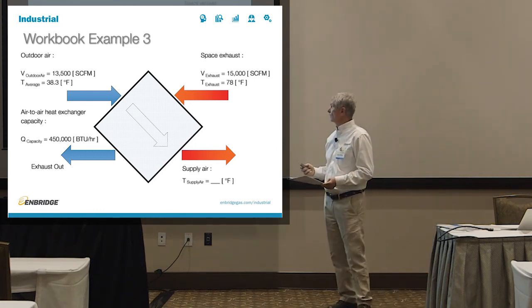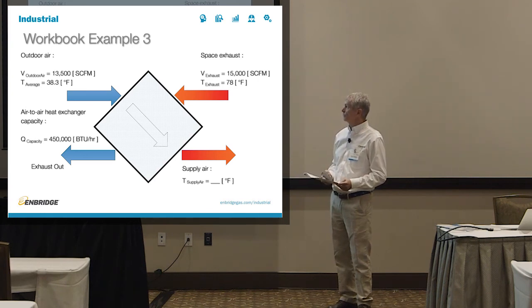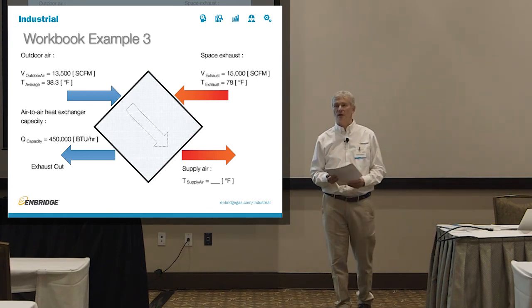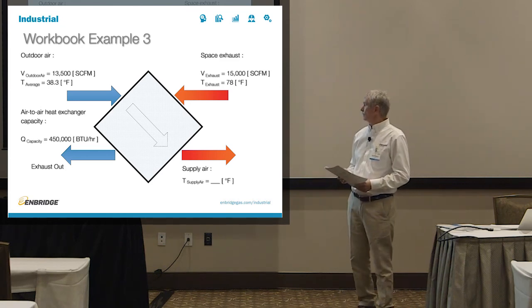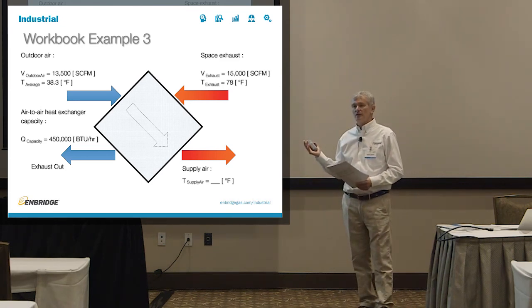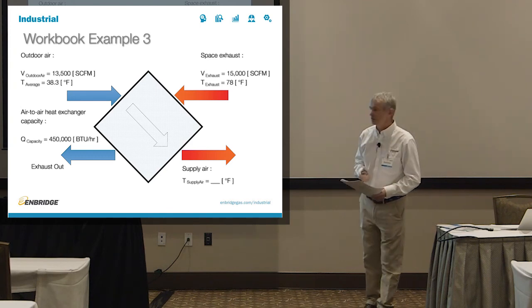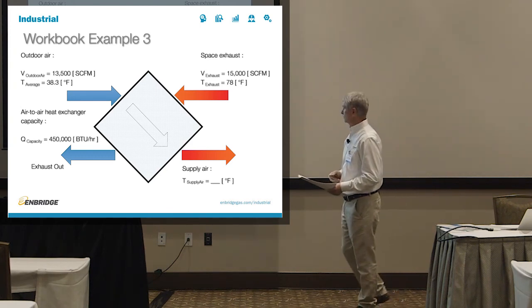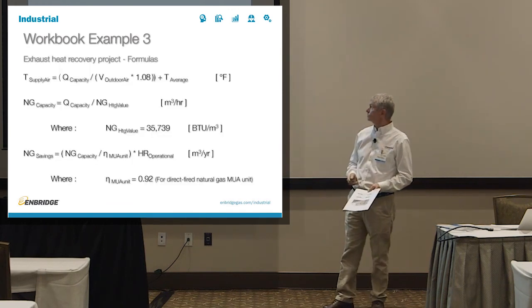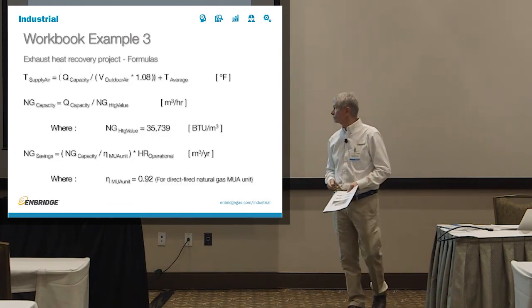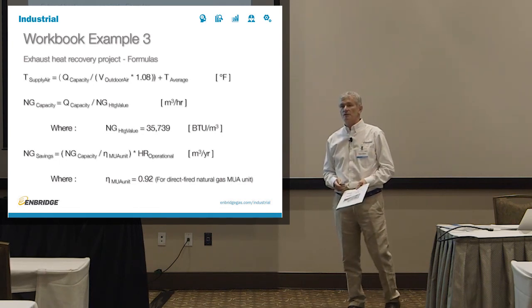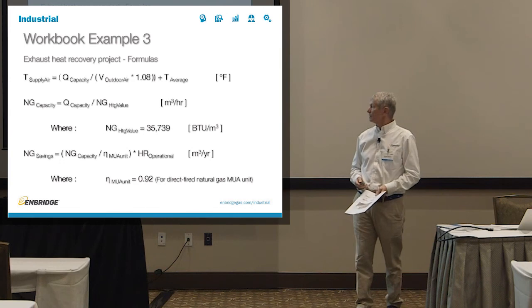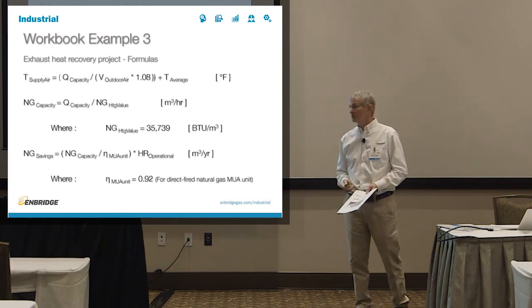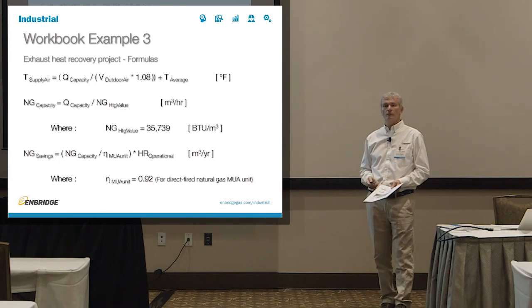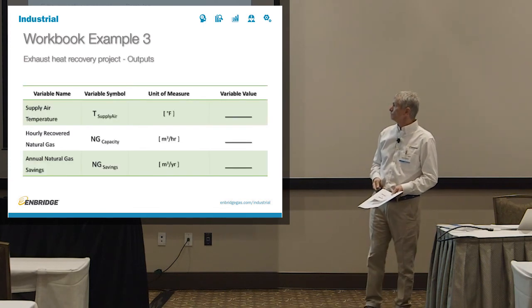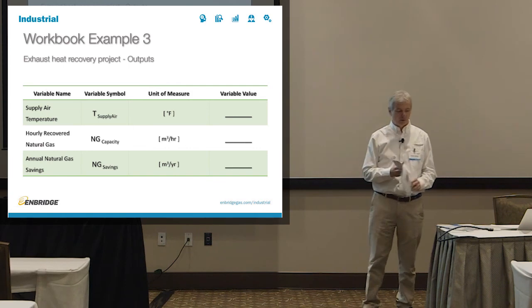So this is essentially what we have. Space exhaust going into the unit and outdoor air, 13,500 CFM of outdoor air coming out through the other side, at 38.3 degrees F, which is the average temperature in the Toronto area for the season. And then we have supply air coming into the facility. What we want to know is what is the temperature of the supply air coming into the facility, how much natural gas will we save with that unit, and we'll fill that into the table below.